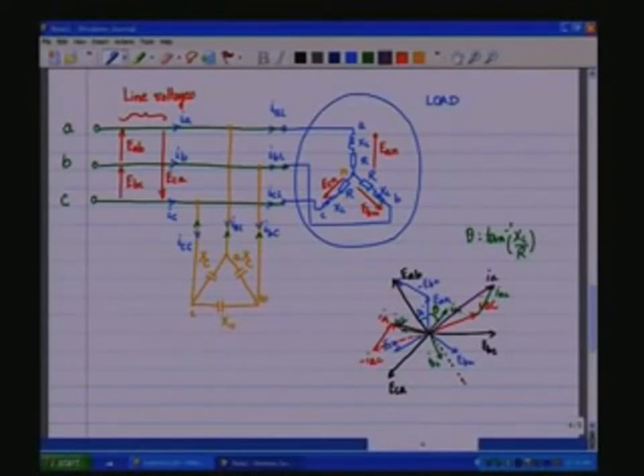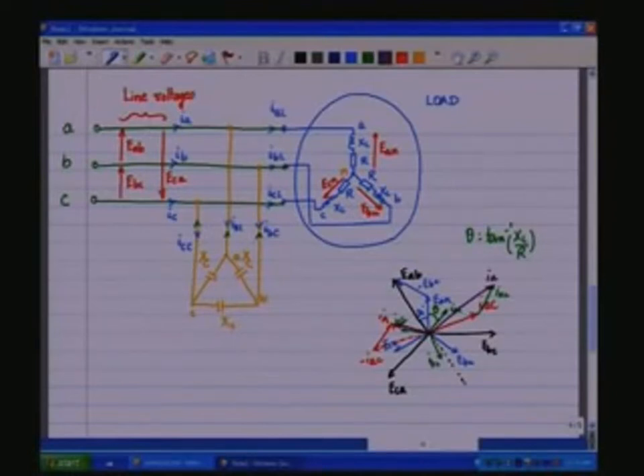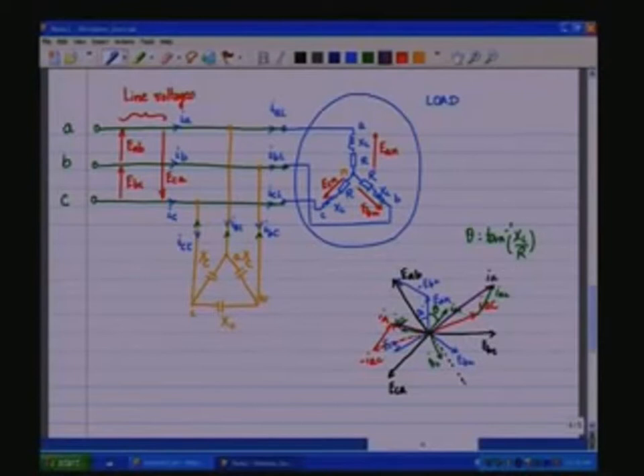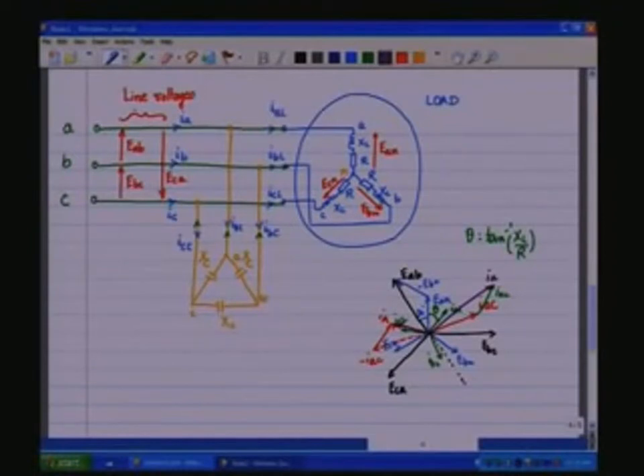So we add a line parallel to I_AL and then we would have I_A — that would be I_A under the condition that we are using this capacitive reactance to pump back the reactive power. We invert the direction of the currents and the resultant I_A is now leading the voltages rather than lagging, which would have been the case with just the RL load. If we adjust the values of the capacitive reactance such that I_AC is adjusted, one can make I_A in phase with E_AB — achieving unity power factor on the line side. That would be the function of capacitance C.